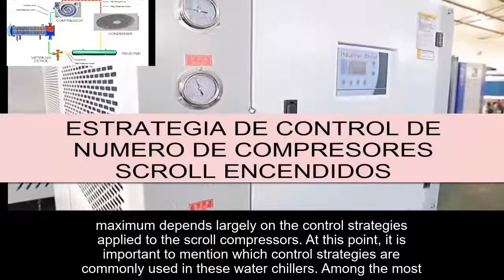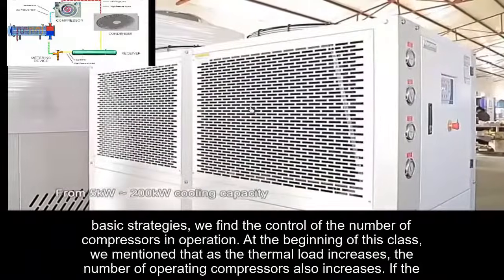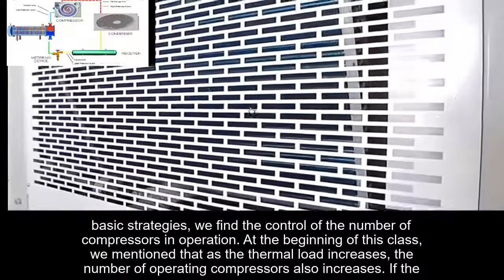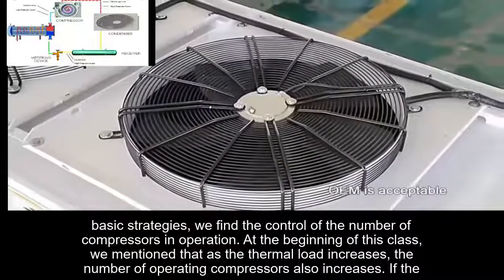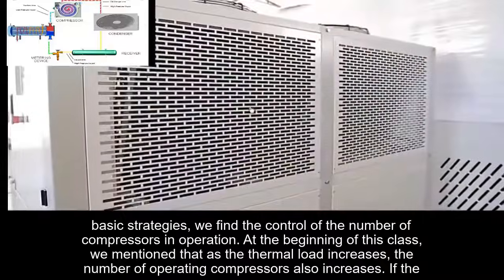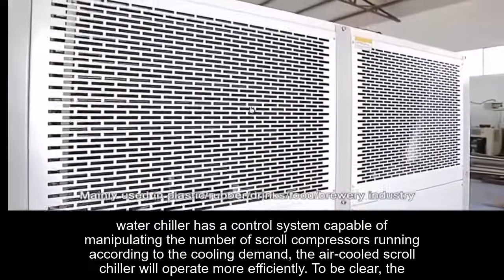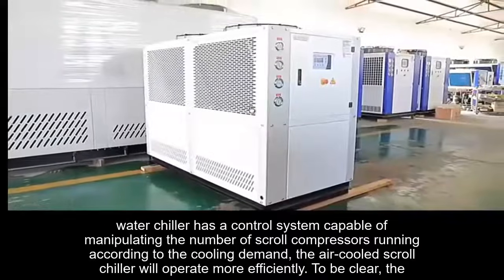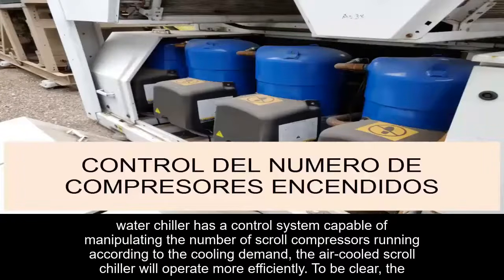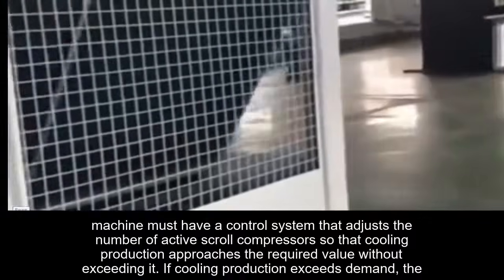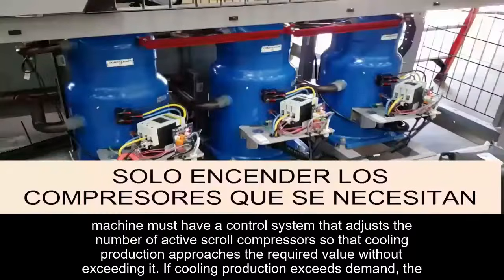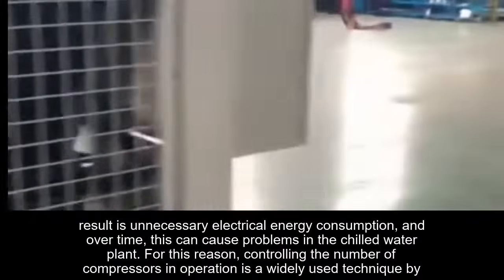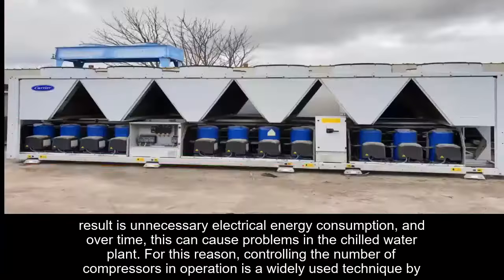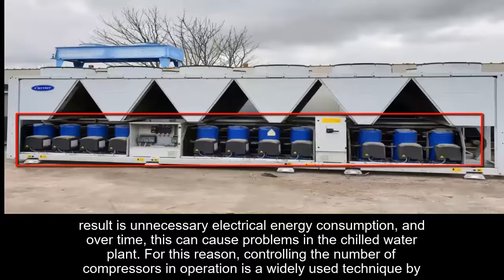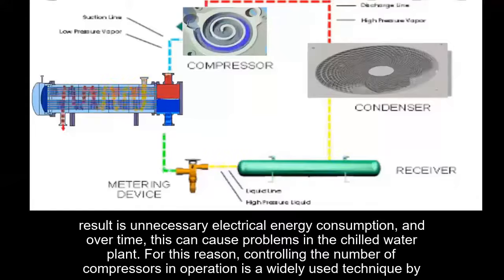At this point, it is important to mention which control strategies are commonly used in these water chillers. Among the most basic strategies, we find the control of the number of compressors in operation. At the beginning of this class, we mentioned that as the thermal load increases, the number of operating compressors also increases. If the water chiller has a control system capable of manipulating the number of scroll compressors running according to the cooling demand, the air-cooled scroll chiller will operate more efficiently. To be clear, the machine must have a control system that adjusts the number of active scroll compressors so that cooling production approaches the required value without exceeding it. If cooling production exceeds demand, the result is unnecessary electrical energy consumption, and over time this can cause problems in the chilled water plant. For this reason, controlling the number of compressors in operation is a widely used technique by manufacturers of air-cooled scroll chillers.